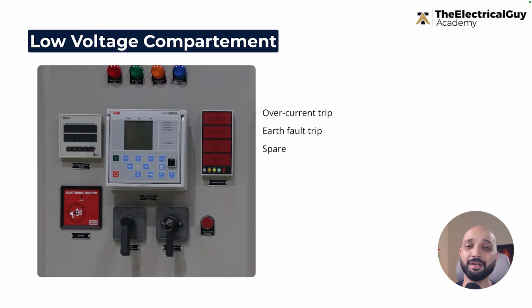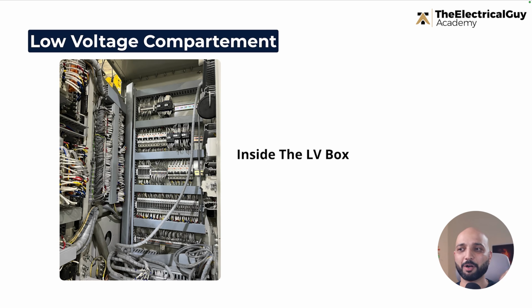Now what we saw is a very basic level of low voltage compartment. There are very complex low voltage compartments as well. Again, that will be based on the requirement. And if you open the low voltage compartment, what you will see is a jungle of wires. So a lot of wires, a lot of logics, and this complexity increases as you add more and more logics, more and more protection functions. So this becomes very critical and also very complex. And of course, there is cost associated with this. So the more logic you add, the more interlocks you add, the more wires you need, the more maybe MCBs and contactors you need. So the cost will go up with that, right?